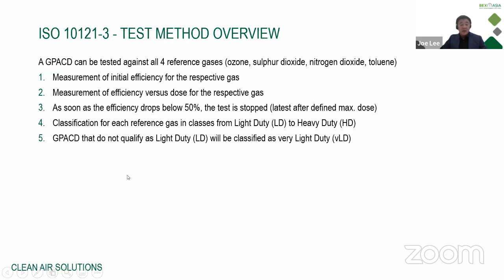The second step, the second challenge, will be the efficiency versus the dosage for the respective gas. So we will pump a certain concentration level into the upstream side of the filters to challenge the filters, and we measure the efficiency of the filters at the downstream side. As soon as the efficiency drops below 50%, the test will stop. And from there, we can classify each reference gas for each filter from light duty, medium duty to heavy duty. So should a GPACD, a molecular filter, not qualify for light duty, it will be classified as very light duty, VLD.